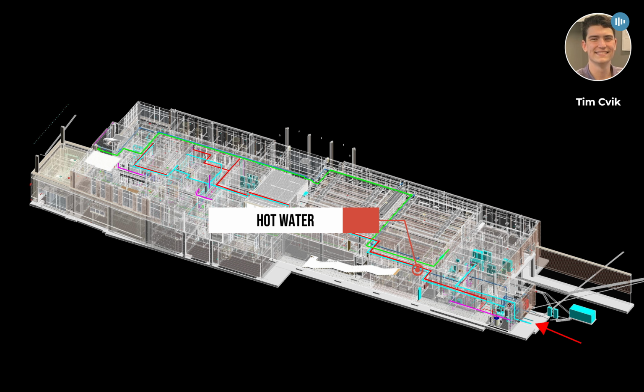140-degree water is then mixed with cold water at a mixing valve to bring the temperature down to 120 degrees to prevent scalding. It is then distributed to all fixtures and devices that require hot water. When placing the pumps and water heaters, be sure to leave clearance so the equipment can be serviced if there are any maintenance issues. Exact equipment clearances depend on the equipment manufacturer.